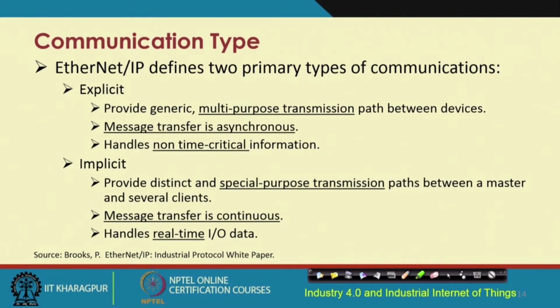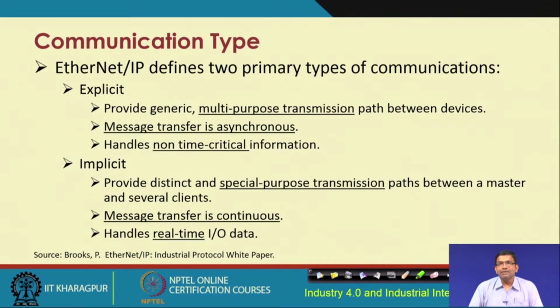So, in EtherNet/IP there are two types of communication, explicit and implicit communication. Explicit communication provides generic multipurpose transmission between different devices, and typically the message transfer is asynchronous in this type of communication. Explicit handles non time critical information. On the contrary, implicit handles real time input output data requirements. Here, unlike in the explicit case where the message transfer was asynchronous, the message transfer is continuous, and implicit communication provides distinct and special purpose transmission between the master and clients.